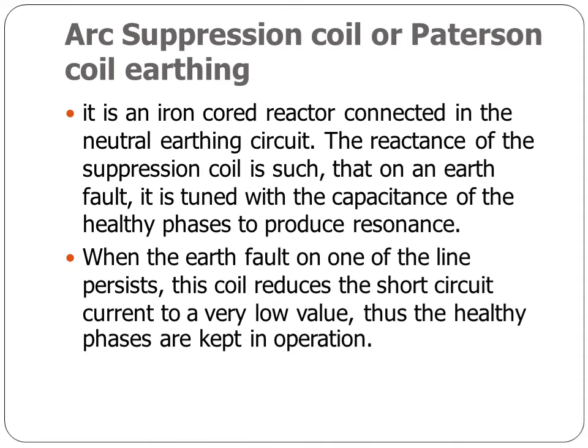Arc suppression coil or Peterson coil earthing. It is an iron core reactor connected in the neutral earthing circuit. The reactance of the suppression coil is such that on an earth fault it is tuned with the capacitance of the healthy phases to produce resonance. When an earth fault occurs on one line, the coil reduces the current to a very low value. Thus the healthy phases are kept in operation. So in a three-phase circuit, this will be very useful.